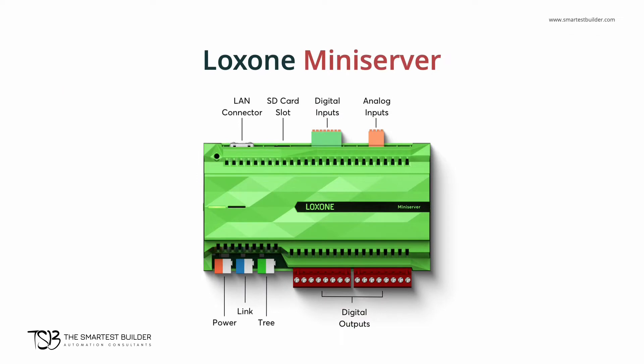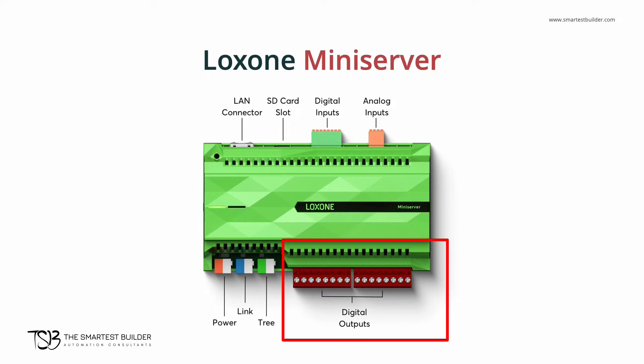The digital outputs are the red terminals that you can see here on the screen. These are voltage-free dry contact relays that produce either an on or off state. They are normally in an off state, meaning the relays are normally disconnected. This state is programmed from the mini server to control a host of things.